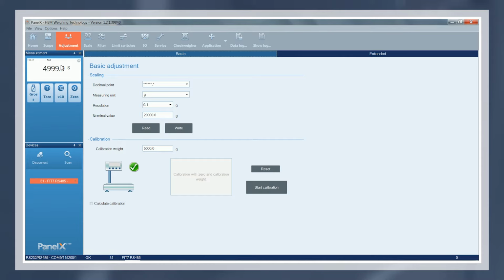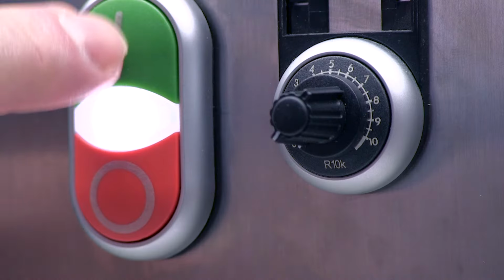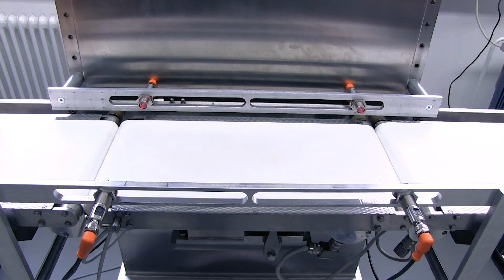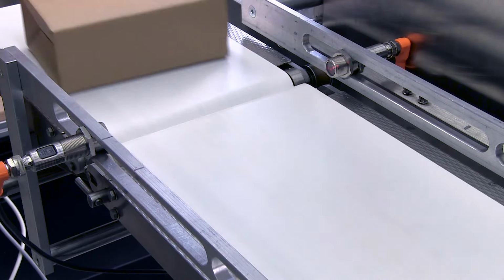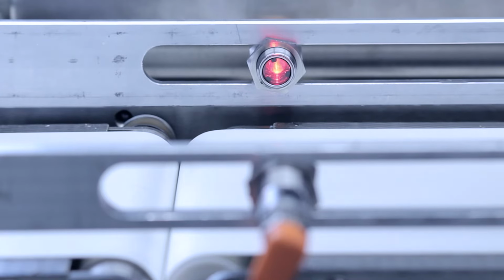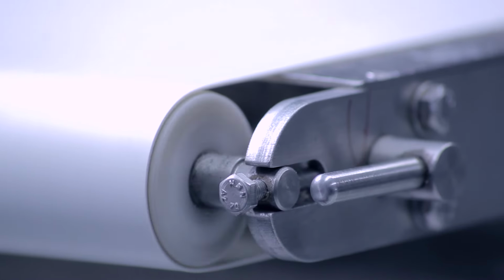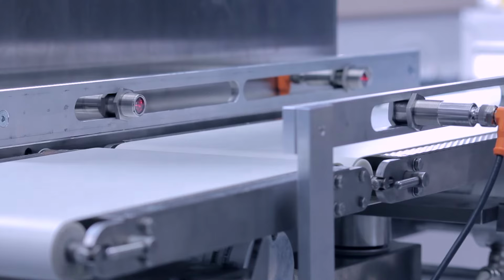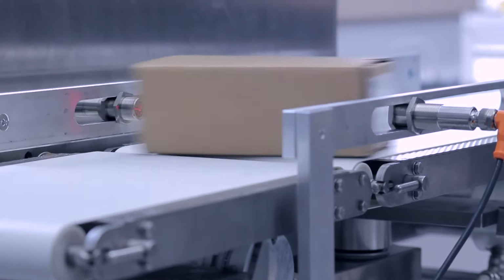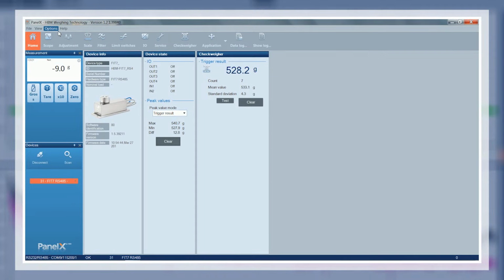We recommend documenting the intrinsic noise and the ambient noise for the Checkweigher. A step-by-step commissioning of systems and machines in the vicinity of the Checkweigher will help identify the system or machine contributing to the noise signal. The noise signal can also be accessed later for comparisons if you notice changes in the noise behavior. An example of this might be because more machines or system components are installed in the vicinity of the Checkweigher.